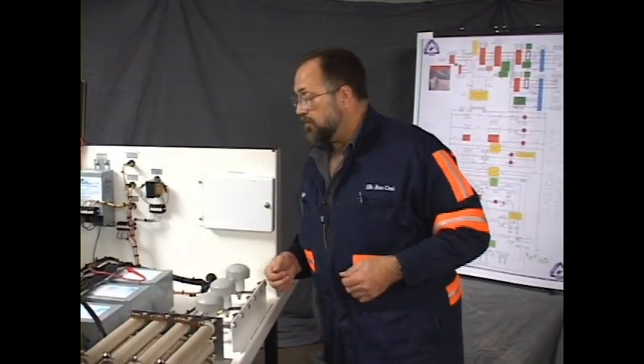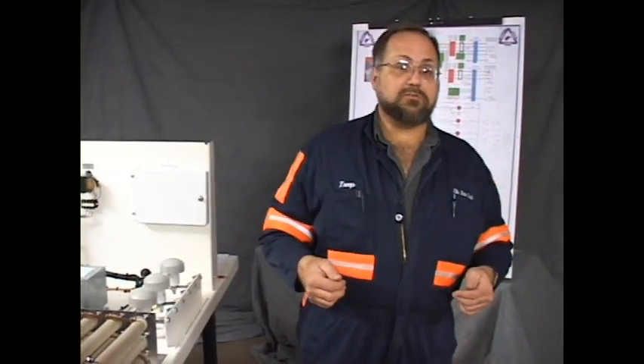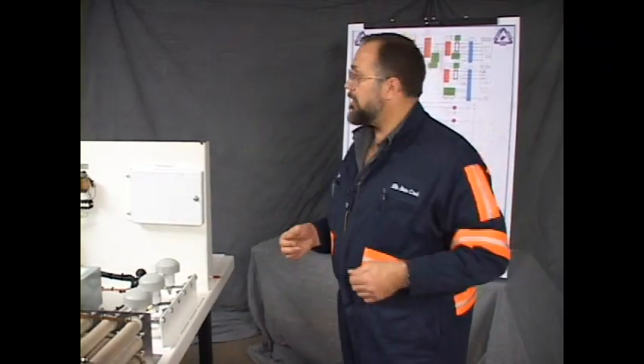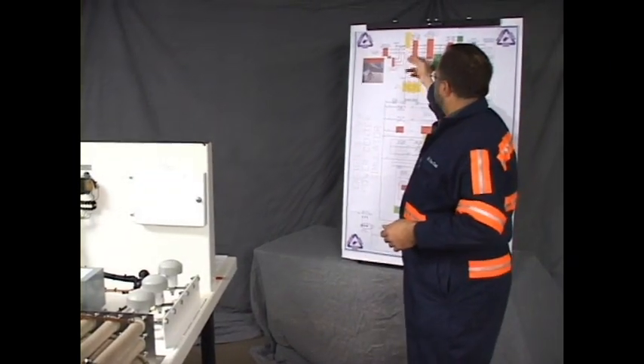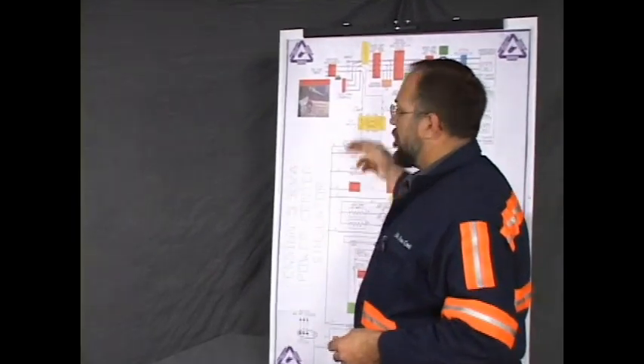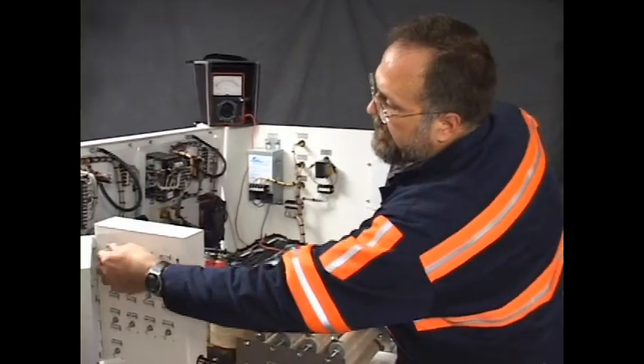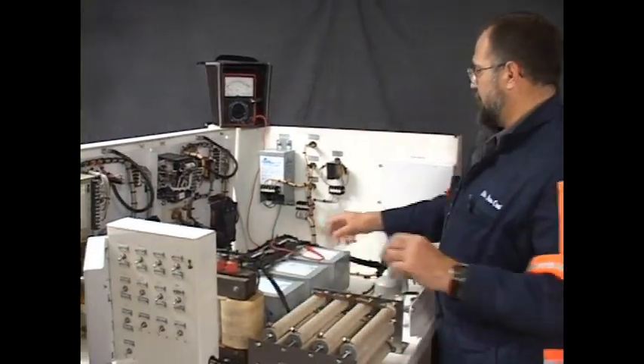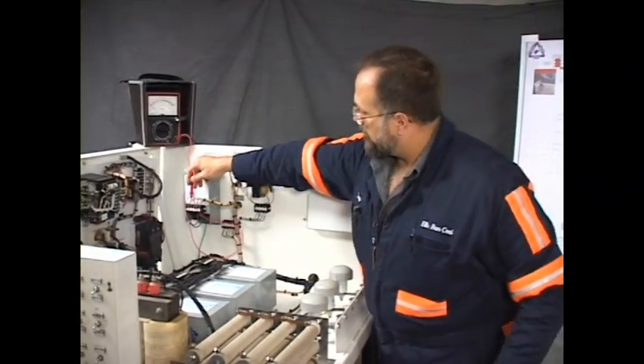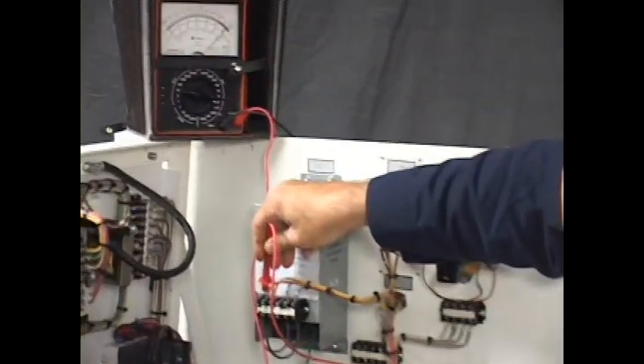And each wire has 2 ends. One probe on one wire, one probe on the other. If you have a circuit, that wire is good. Just as you would follow a map to a certain destination, you would go from landmark to landmark. You start at one point and follow from landmark to landmark. That's the same way that you troubleshoot in a linear fashion. I'm going to put the switch back, take the problem off, and the wire is good.